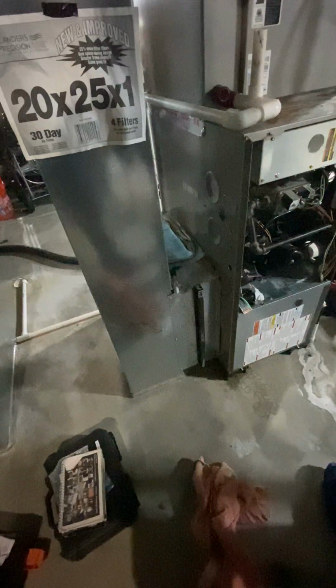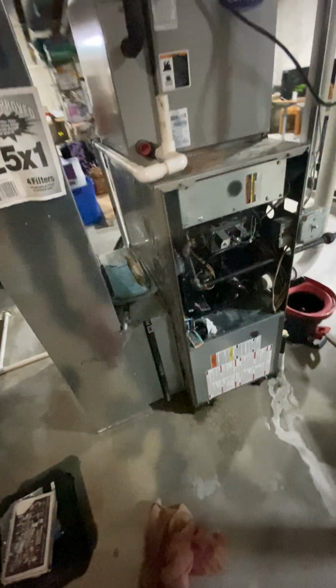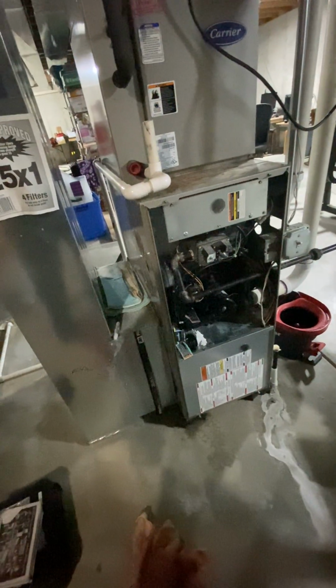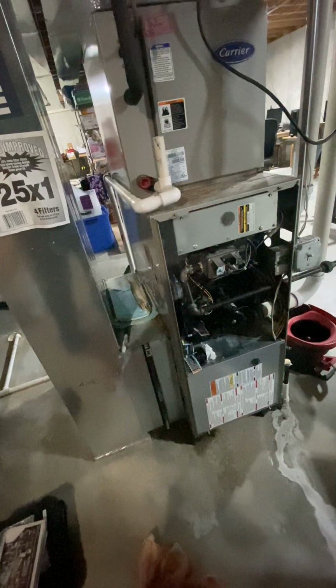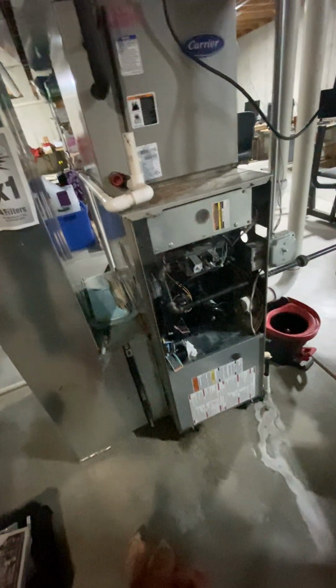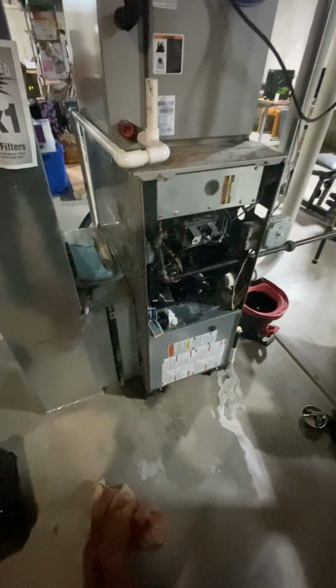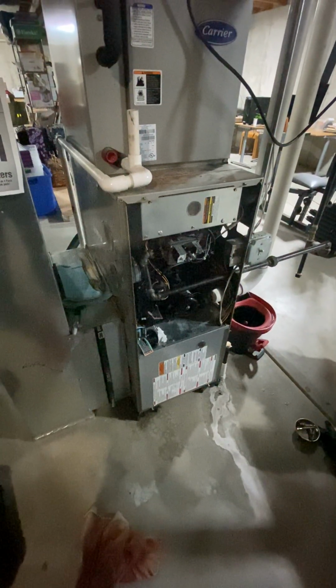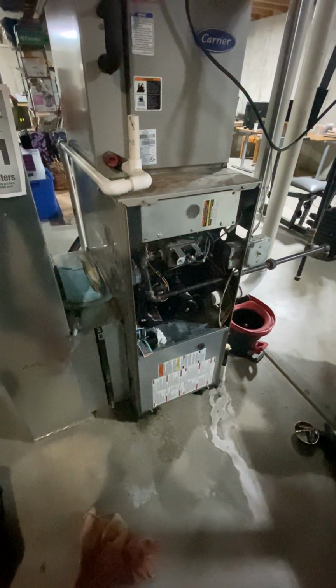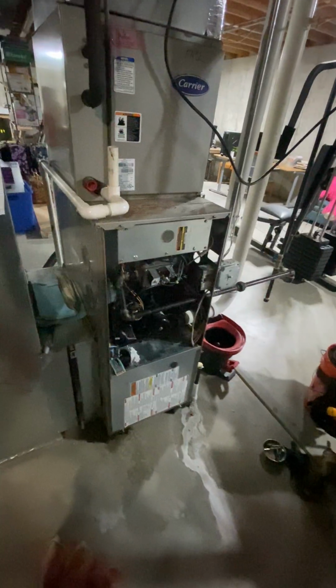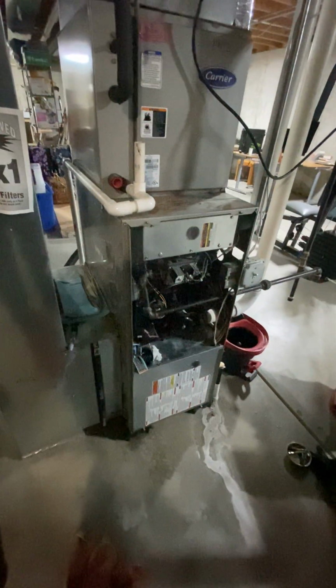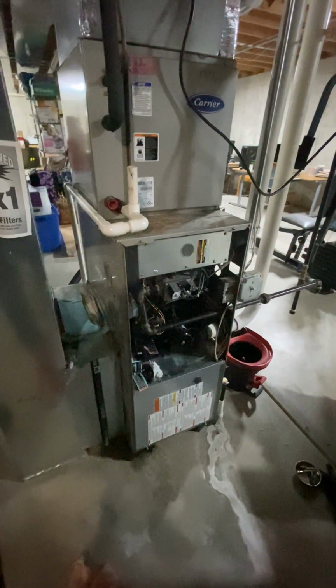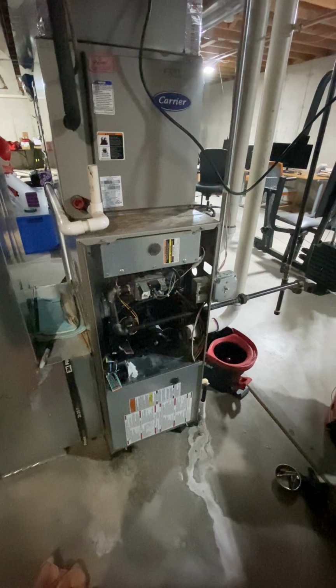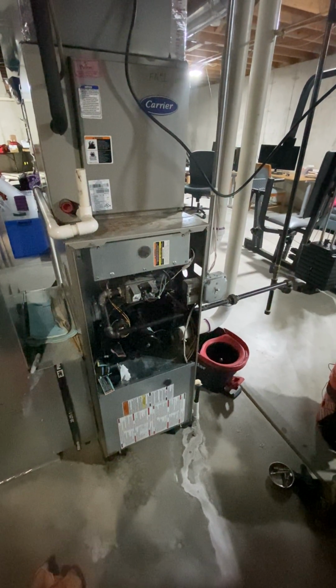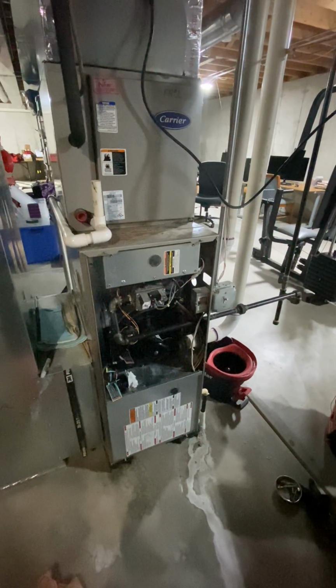Also, I would buy different air filters. The MERV rating you're using, a 14, is too high for these furnaces. When you have a high MERV rating, it's harder to push air through here. If you slide an air filter in there, it slows down that motor and puts more stress on it. So I would use single digits for these typical systems. In the newer furnaces, the blower motor is built better compared to the ones you have now. If you're going to use a MERV rating, use something between 5 and 7, because they put a lot of stress on those blower motors. I wouldn't advise using these.